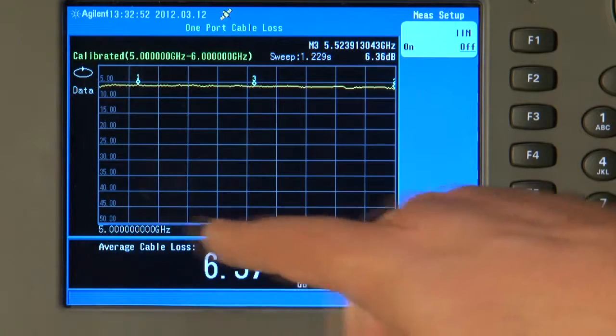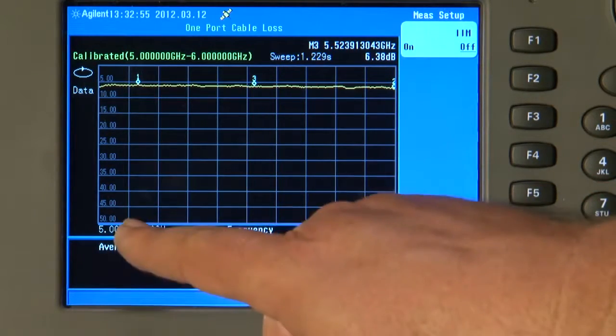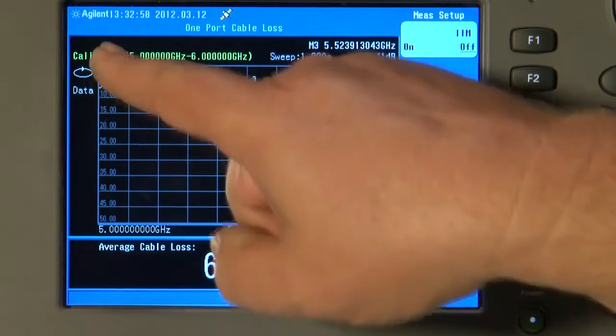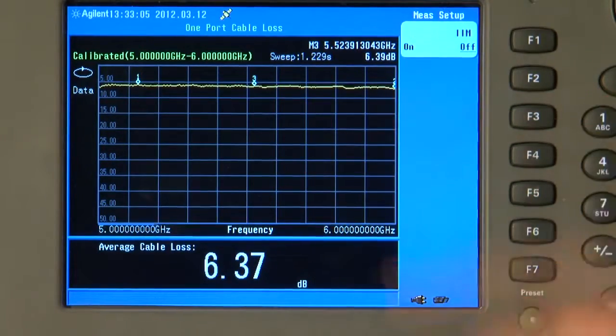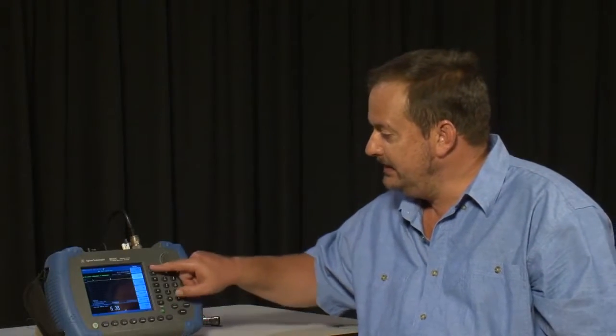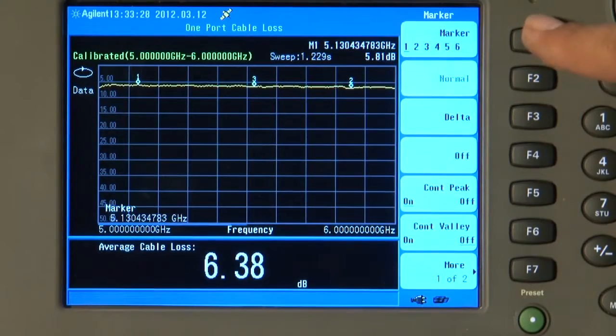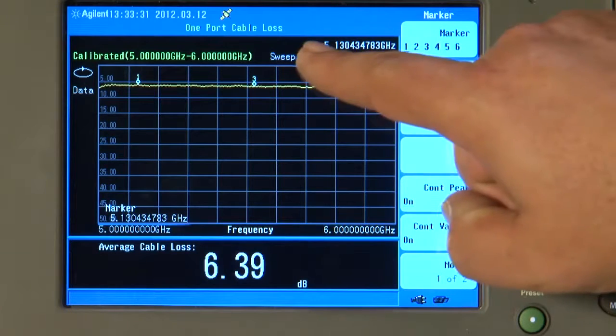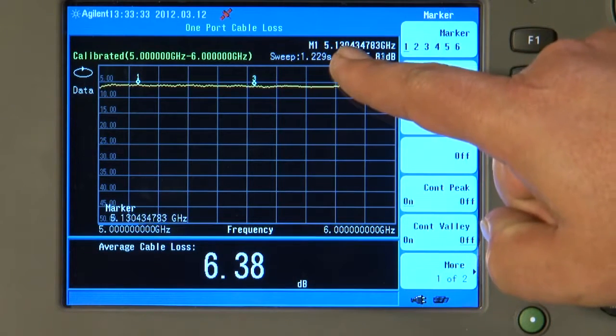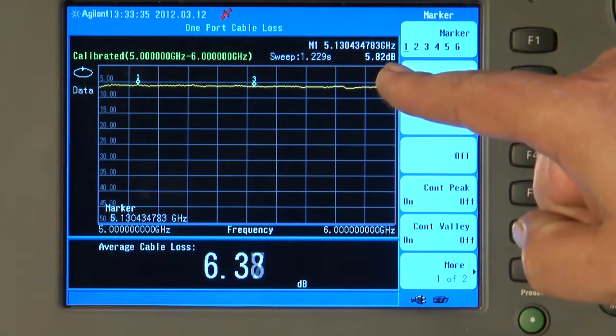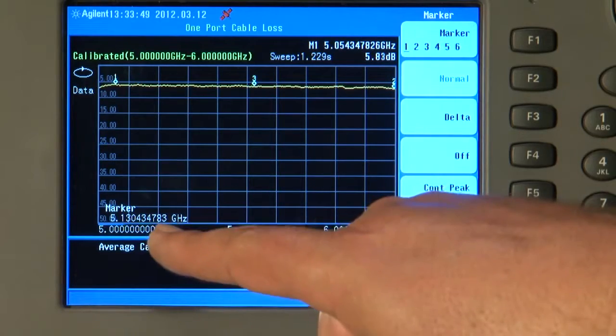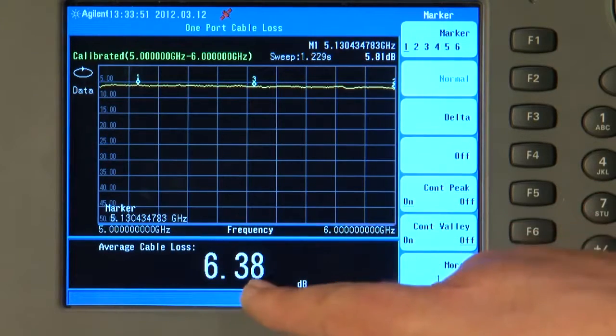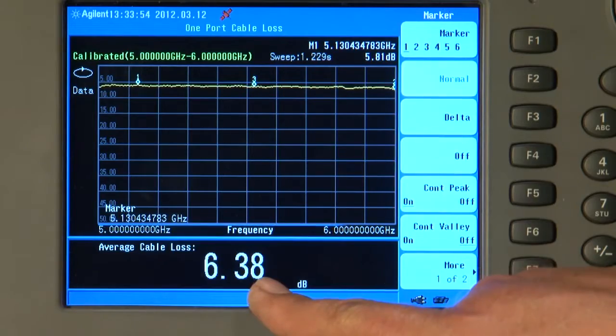So the X axis is again still showing frequency, sweeping between 5 and 6 GHz, but the Y axis is now giving us a measurement of cable attenuation in dB across that frequency range. We can press the Marker button and select any of the six markers. So here Marker 1, you can see at 5.1 GHz the cable has an attenuation of 5.8 dB, and at the bottom of the screen it tells us the average cable loss across the frequency range of 5 to 6 GHz, and currently the average cable loss is about 6.4 dB.